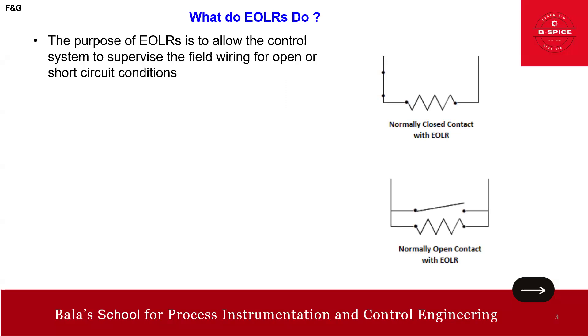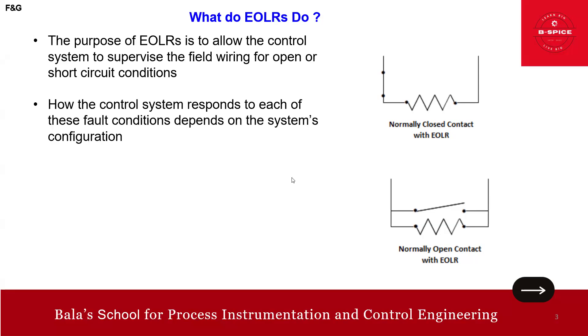The purpose of EOLR is to allow the control system to supervise the field wiring for open and short circuit conditions. The typical normally closed contact is in series, and the normally open contact is in parallel. However, how the control system responds to each fault condition depends on the system configuration.